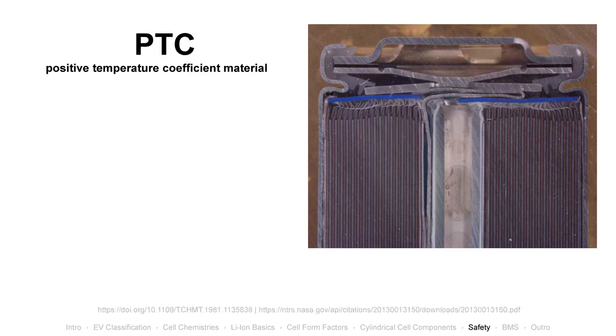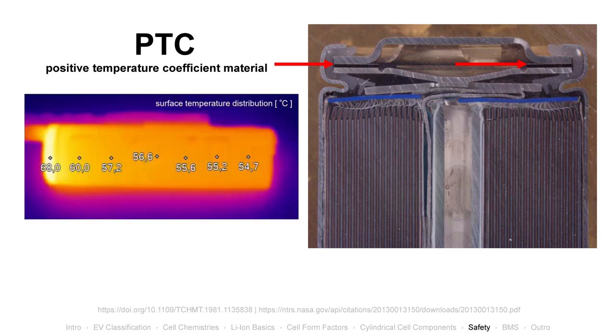A PTC, short for positive temperature coefficient, is an electrical conductor which experiences a resistance increase as temperature rises. It's placed in series with the cell into its cap and reduces current flow at high temperature. In this picture, it's the dark ring between the positive terminal and the burst disc. Tripping the PTC permanently changes its internal resistance by up to a factor of 2. The cell loses efficiency and emits more heat from that point in time onwards, up to 3.5 watts, so an overcurrent or short circuit event on the cell should be avoided for its whole lifetime.